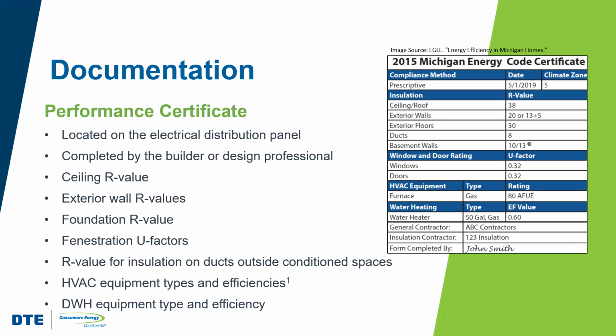There should also be a performance certificate for the entire home. This should succinctly list all the key thermal and efficiency performance data for the major building systems, the home envelope elements, the insulation, the roof, walls, floors, windows, doors, as well as the HVAC and water heating system. And rather than handing this certificate to the homeowner in a closeout package, this certificate should be permanently affixed to the main electric distribution panel. That way, it doesn't get misplaced or lost if the home changes hands. It's readily conveyed to the new owner. And care should be taken so that this certificate doesn't obscure any other important information that may be on that panel, right? We don't want to cover up circuit names and things like that when we're affixing this to the electrical panel.